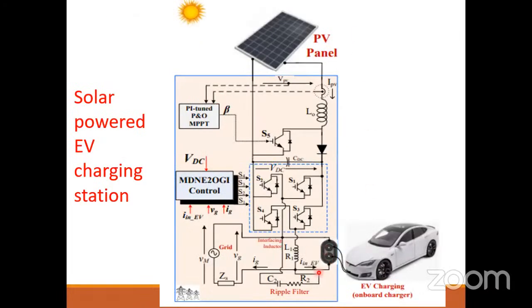For example, suppose we estimate the harmonic demand from the load side, and assume the estimation error is 1% higher with respect to the load demand, mainly the nonlinear current. Then the inverter will also generate 1% higher harmonic current, and that extra current will come on this PCC terminal. But the load will consume exactly according to demand, so the extra 1% will go inside the grid. This means, because of overestimation, you are polluting the grid.